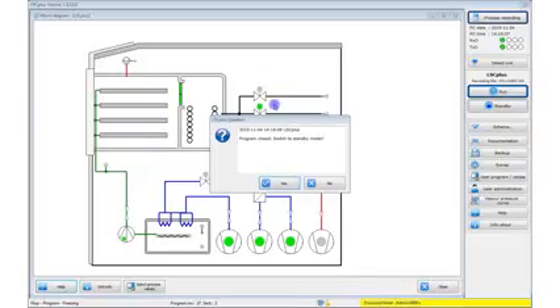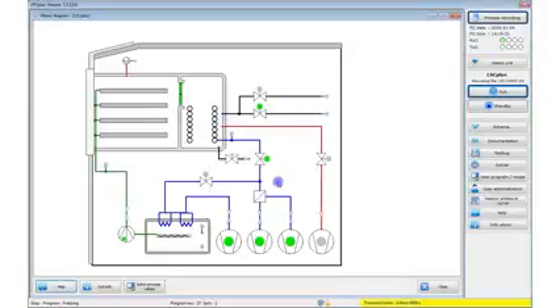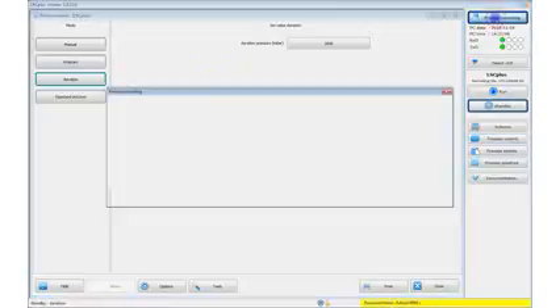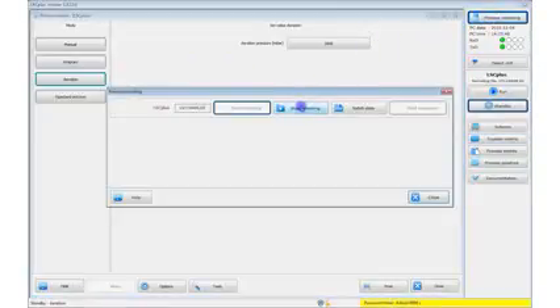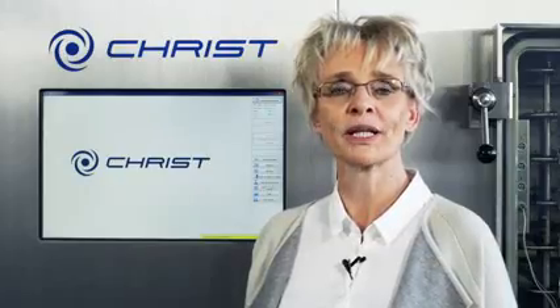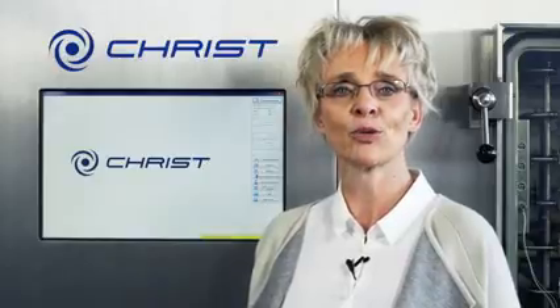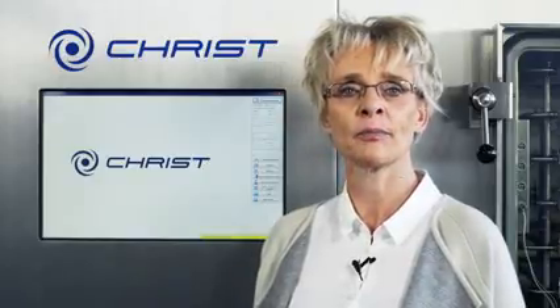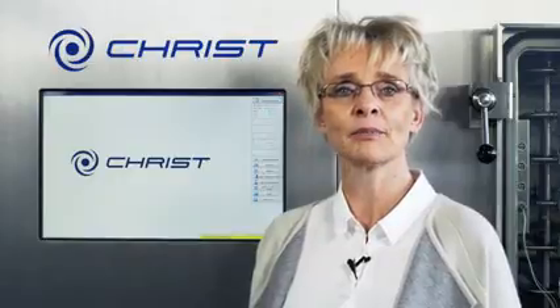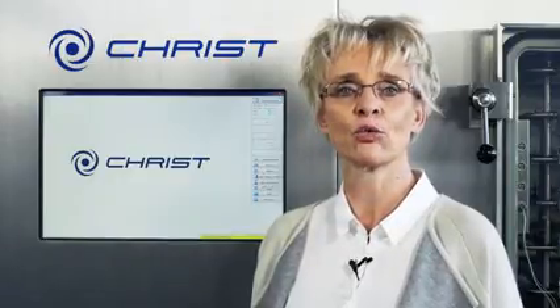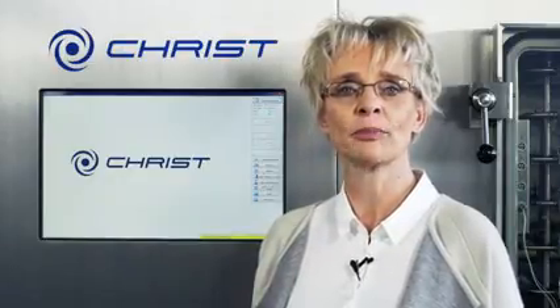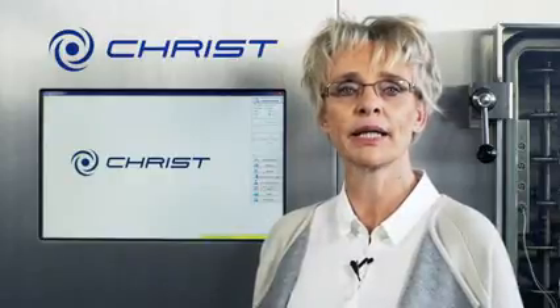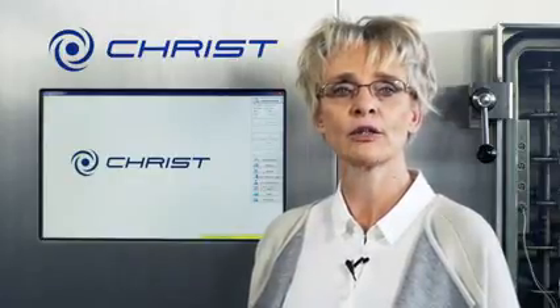Once the freeze-drying program has finished, it has to be terminated. You also have to stop process recording. All the processes you have recorded are shown under Documentation. All data is stored in the integrated database in compliance with the relevant GMP and FDA guidelines and is available whenever needed for process documentation.